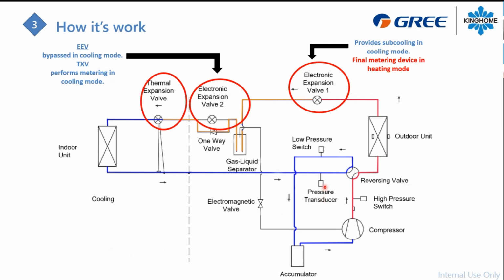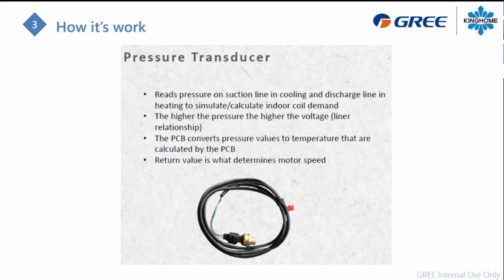On this, we saw here the low pressure switch and the high pressure switch, and you also have a part called the pressure transducer. The pressure transducer here is located on the suction line, so it will read the pressure in cooling mode, and it will be your discharge line in heating mode. And we will use this device to calculate the coil demand.